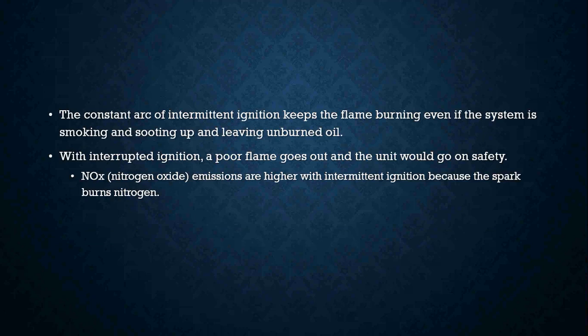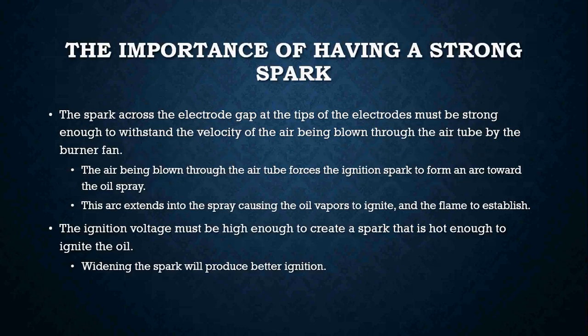be operating. Okay, the constant arc of intermittent ignition also keeps the flame burning, even if the system is smoking and sooting up and leaving unburned oil in the chamber. With interrupted ignition, a poor flame goes out and the unit goes on safety. Nitric oxide or NOx emissions are higher with intermittent ignition because the spark burns nitrogen.